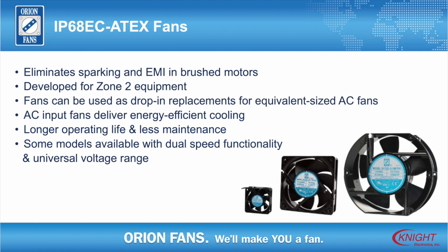EC-ATEX rated fans combine energy conservation with maximum protection. These EC fans are ideal for power-hungry applications that require a spark-proof fan design to thwart potentially dangerous and harmful situations. Durable performance is particularly important for applications involving explosive atmospheres or flammable gases. Developed for Zone 2 equipment, the implementation of IP68 fans into a design eliminates the possibility of an explosion or fire. The IP68 rating specifies an enclosure that can withstand dust, dirt, and sand, while also being resistant to submersion in up to 1.5 meters of water for up to 30 minutes.